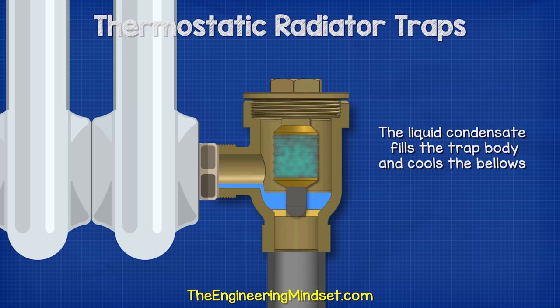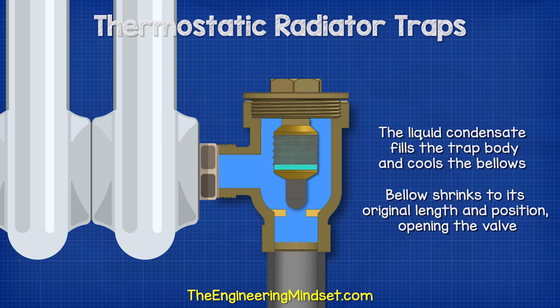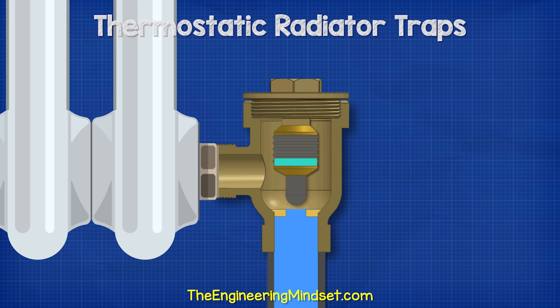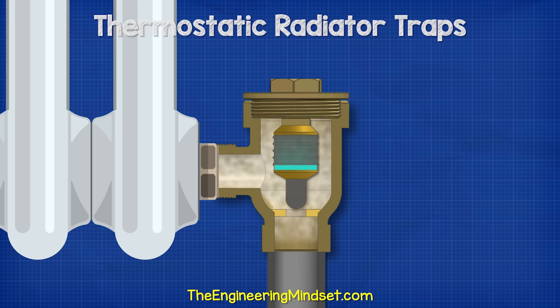The liquid condensate fills the trap body and draws heat out of the bellow. This allows the pressure inside the bellow to reduce, and the bellow shrinks to its original length and position, opening the valve. The steam then pushes the condensate out, the trap closes, and the cycle repeats.